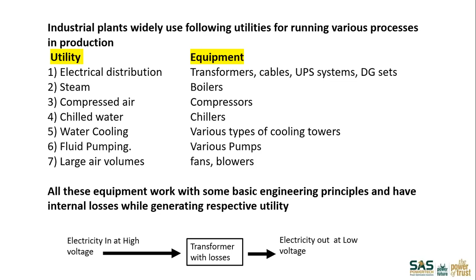If you come across any figure between 70 to 80%, it is very difficult to suggest modifications. But if you get an efficiency somewhere between 20-23%, you can definitely doubt the selection of the pump for that particular application. Something similar happens for all these equipment when you analyze them. Some standard investigations which we carry out when we do energy audits are electrical distribution loss, motor efficiencies, motor pump efficiencies, pump selection, compressor, fan and blower efficiencies, typical specific energy consumptions like kW per CFM, leakage quantification, and use of compressed air. All this we normally do.